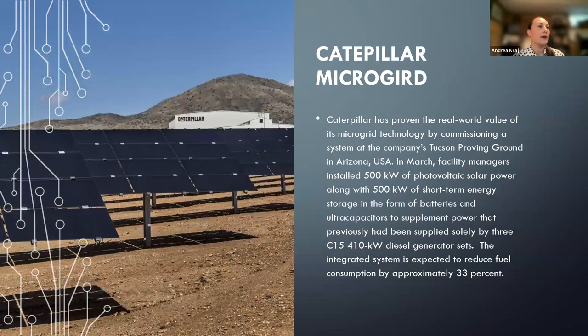The Caterpillar microgrid is one that is in the proving grounds in Tucson, Arizona, and it is around 500 kilowatts. It's got PV along with short-term energy storage in the form of batteries and ultracapacitors to supplement power. It also uses a diesel genset there. It has reduced fuel consumption by about 33%.